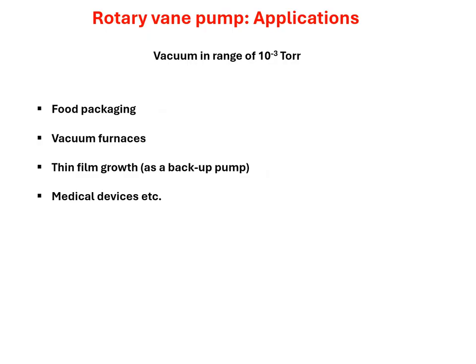The rotary vane pump can create vacuum in the range of 10² to 10⁻³ mbar. There are many applications of the rotary vane pump.